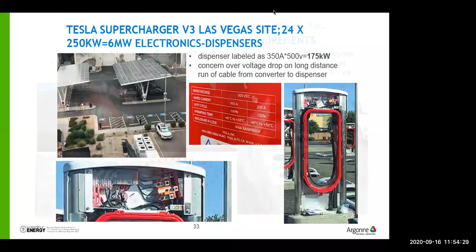In the middle of the photo in the upper left, you can see 6 black dots. These are the top of the power converters. Next slide. Those are these power converters. There are 6 cabinets, and they have 4 outputs each. On paper, these each put out a megawatt, but the panel board on the left, that big white box, is nameplate rated at 4,000 amps. So even though it could pull a lot more current from the grid side, it's limited to that.